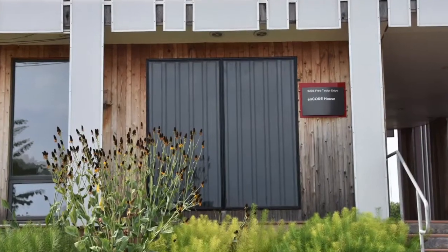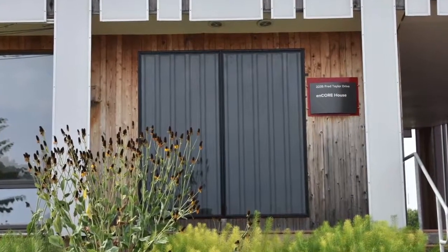The solar thermal hot air system operates in 2 general modes that depend on whether the home needs to be heated or cooled. In the wintertime, when the home needs to be heated, the panels draw in return air from the interior and can increase the air temperature by up to 60 degrees Fahrenheit. In this configuration, small inline fans connected to the panel system draw in air and propel it through insulated ductwork to a phase-changing material plenum, also known as a PCM Plenum. The PCM Plenum contains a hydrated salt which changes phase at 86 degrees Fahrenheit, the supply air temperature for the conditioned space. This PCM essentially works as a thermal battery for the home. It is insulated from the conditioned environment and can store up to 30 hours of heating for EnCORE once it is fully charged.